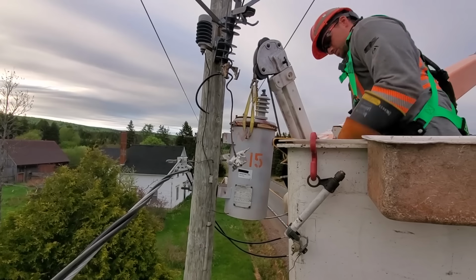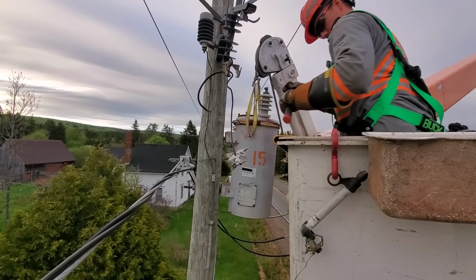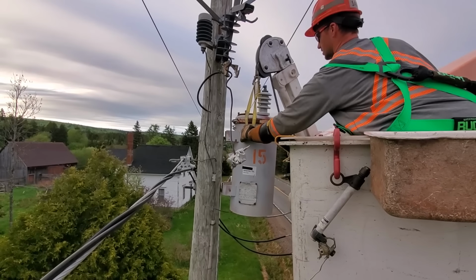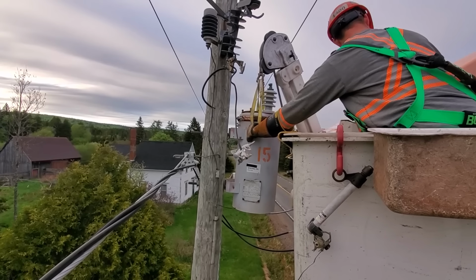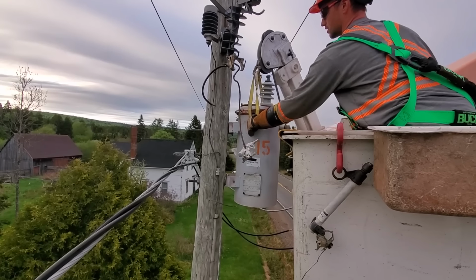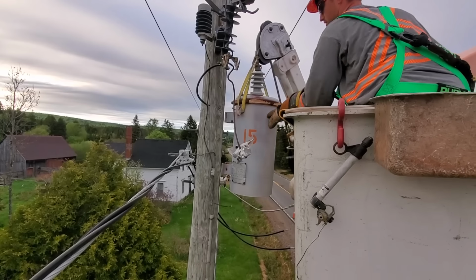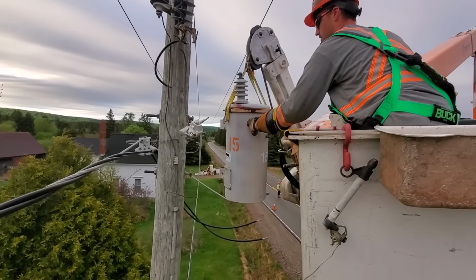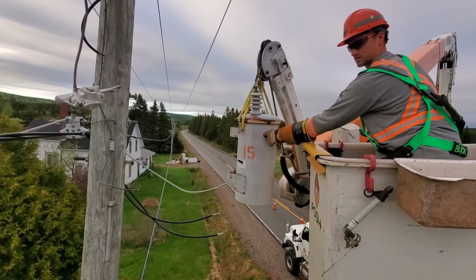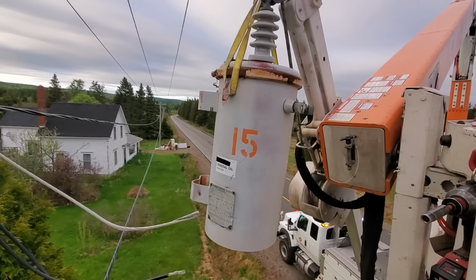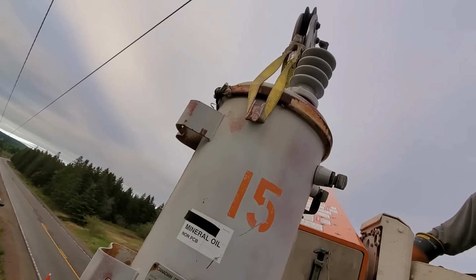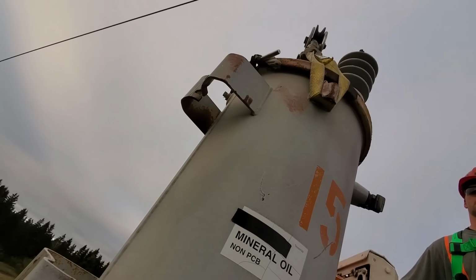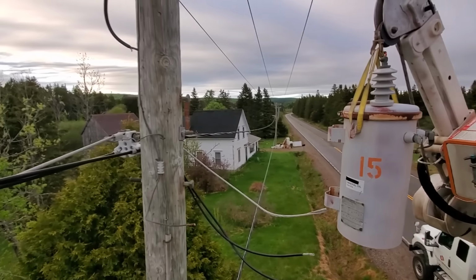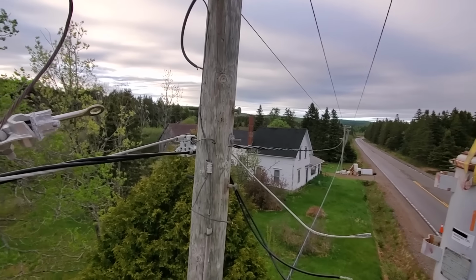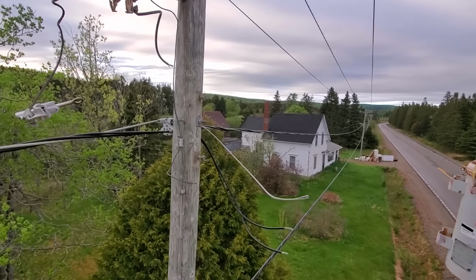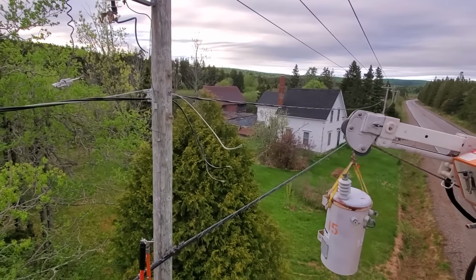Just loosening that nut off a little bit more. And there she goes. You'll see when he backs away here on the bracket of the transformer, it's actually labeled on the diagram that they're called an anti-jumping device or something to that effect. It's just little fins on the underside of the transformer so that once it sits in the bolts, if there's a vehicle accident, the transformer's not going to simply jump up and off those bolts. You do have to kind of get quite a bit of upward tension, wiggle it around a little bit.